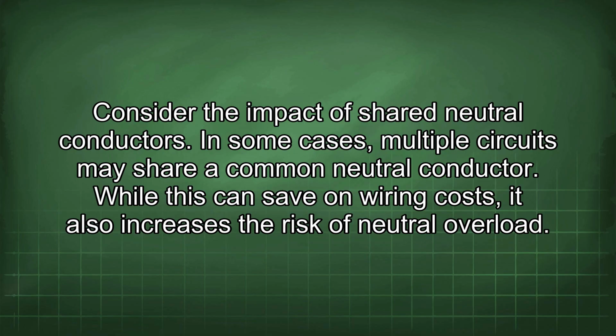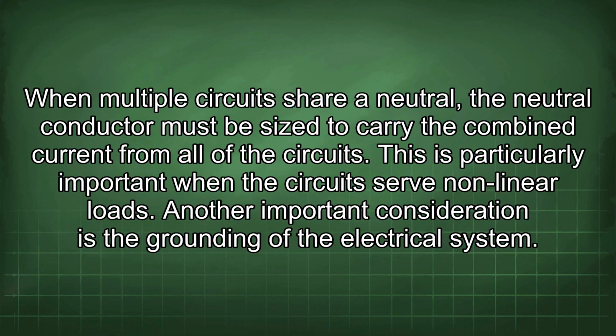In some cases, multiple circuits may share a common neutral conductor. While this can save on wiring costs, it also increases the risk of neutral overload. When multiple circuits share a neutral, the neutral conductor must be sized to carry the combined current from all of the circuits. This is particularly important when the circuits serve nonlinear loads.